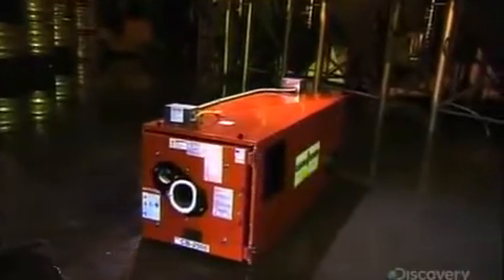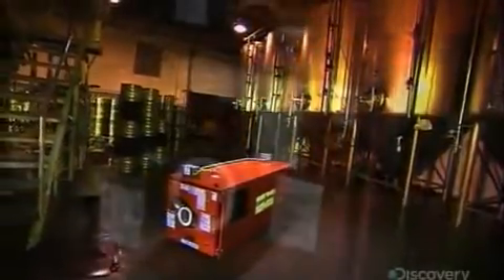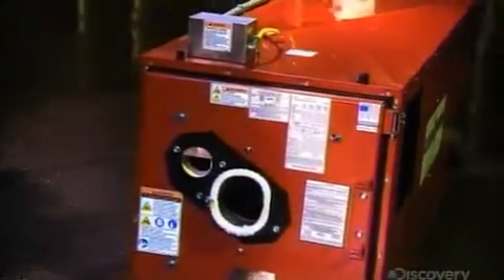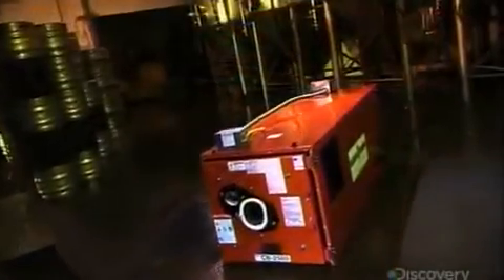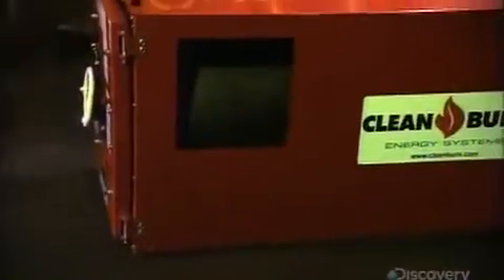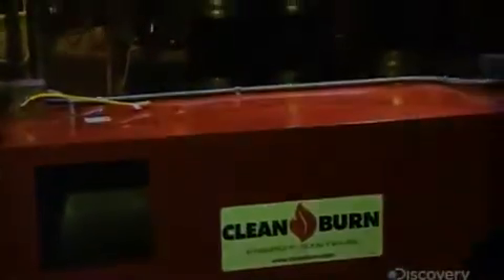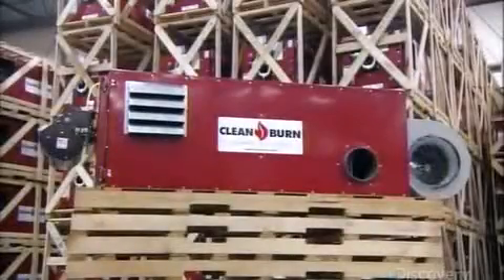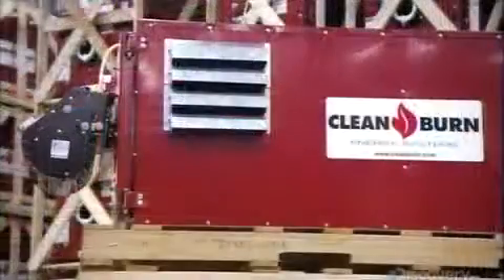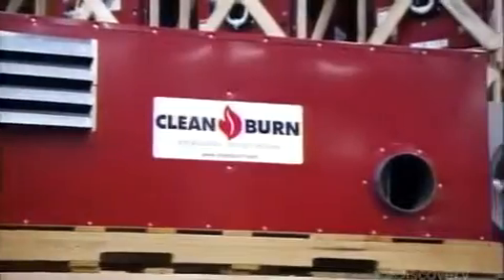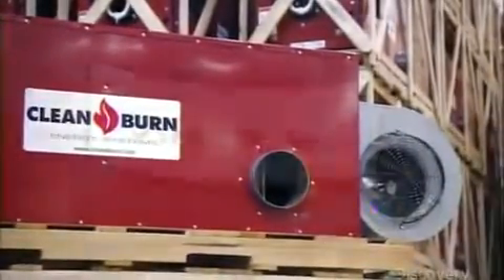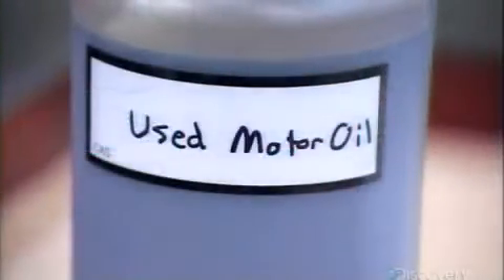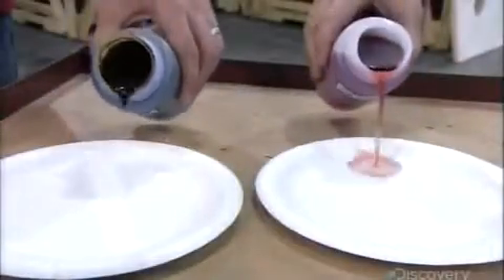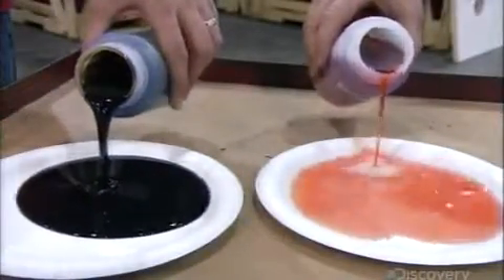Used oil furnaces generate heat by burning used oil without having to refine it. These furnaces are found in automobile shops, maintenance facilities, and construction sites. Transport fleets and trucking companies also use them to turn the used oil they produce into heat for their facilities. It takes a special furnace to burn used oil. Used oil is thick and dirty compared to residential fuel oil and must be turned into a fine mist to burn properly.